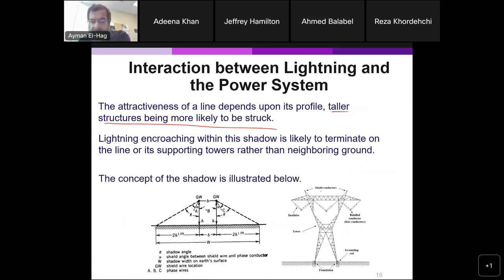Okay, so here, this is an overhead line. We have here the shield conductor. This is a typical single circuit, and everything is horizontal. This is phase A, B, and C, and these are the shield conductors to protect. Your objective basically is that when a lightning strike hits, it hits the shield conductor. The shield conductor's objective is basically to take this surge to the ground, distribute it to the ground, and protect your overhead lines. So this is called the angle of protection. Here are phases A, B, and C, and this is the angle that protects the overhead line.